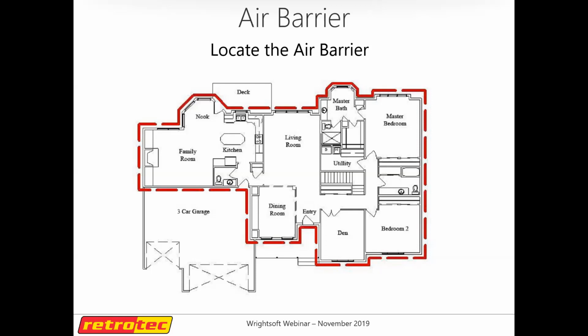It's good to know where that point is, because for more complicated houses, it may not be that easy to determine. If you're just looking at a drawing like this one here, like I said earlier, it's wherever that boundary is that's going to separate inside from outside, and it's going to involve your conditioned space, but not your garage, or a storage building that's unconditioned, that's attached.